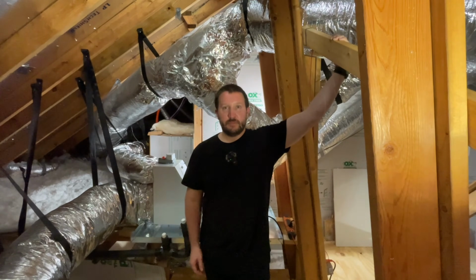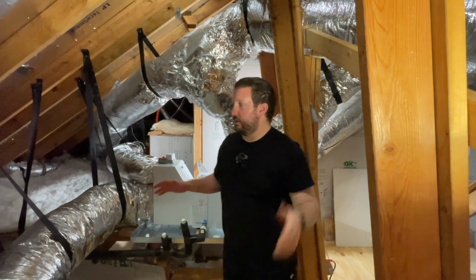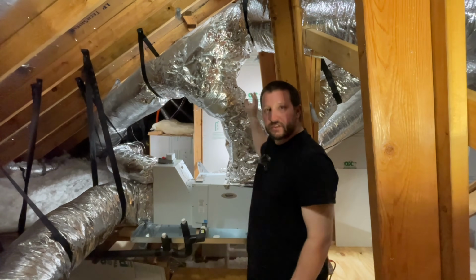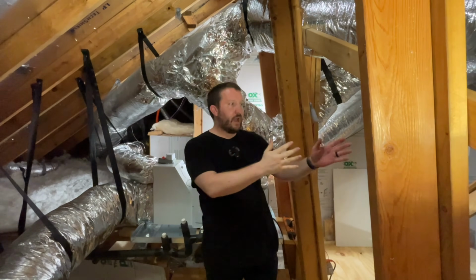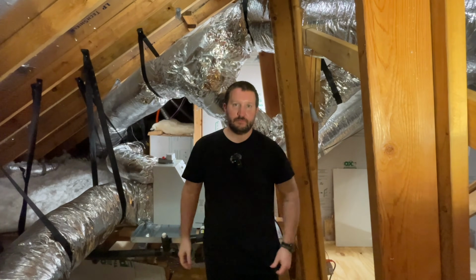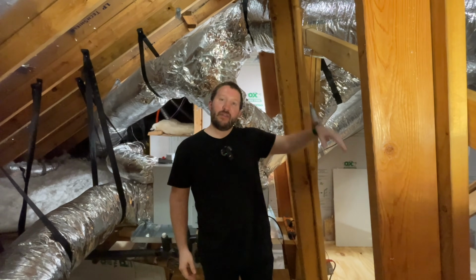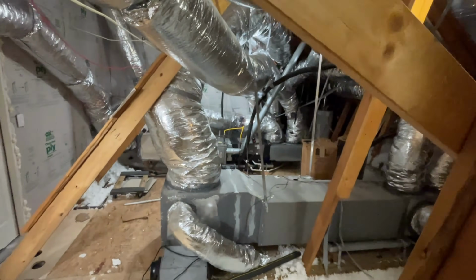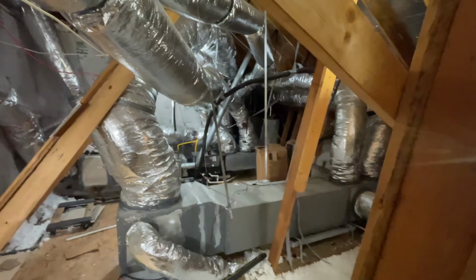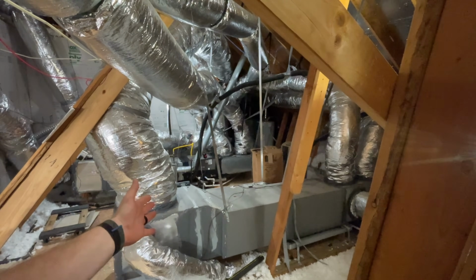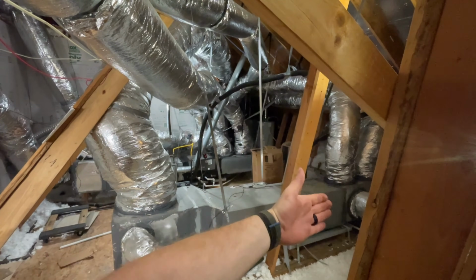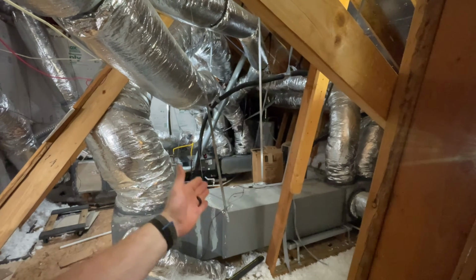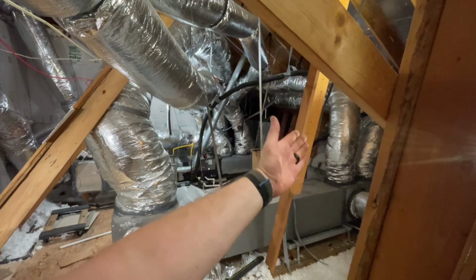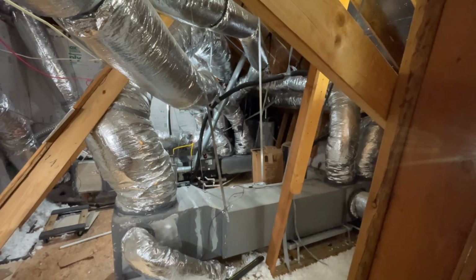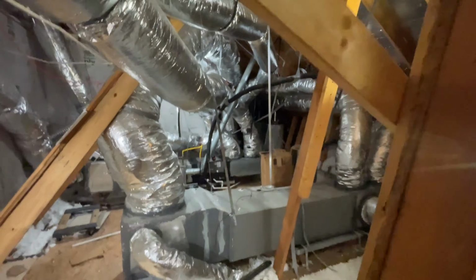Quick recap: return, supply. Do not mount it to your regular AC system. Do not supply the air to the back side of your AC unit, because that air conditioner is just going to rehumidify the air. If this is the return of my air conditioning unit and that is the supply, put the dehumidifier's hose, the ductwork, on the supply side or somewhere wherever your humidity is bad.